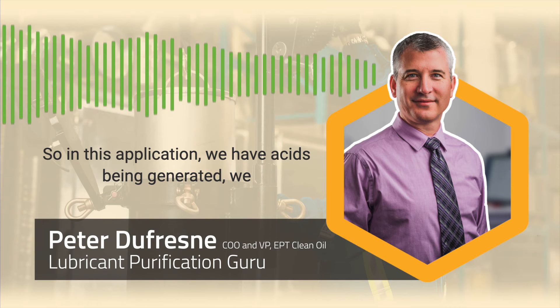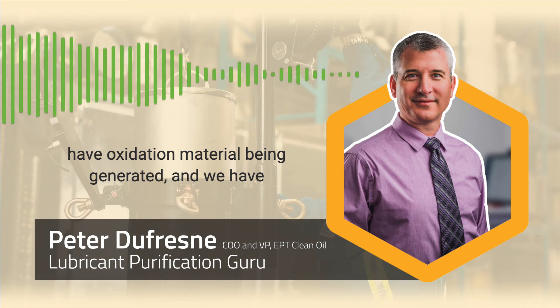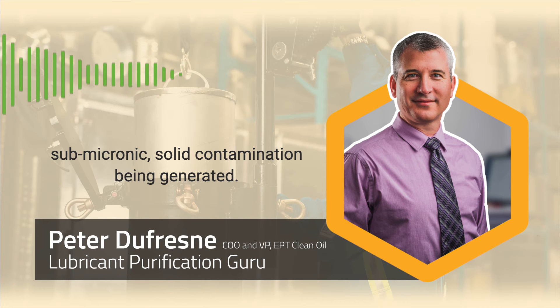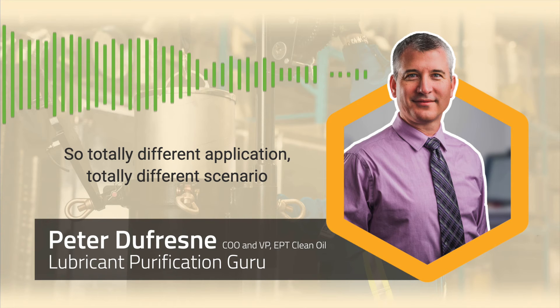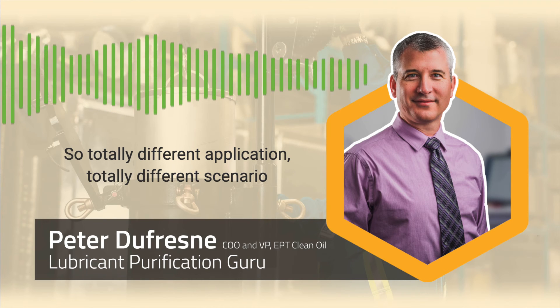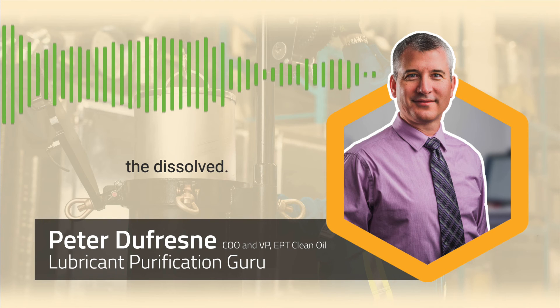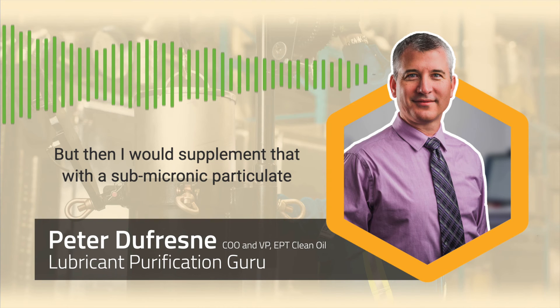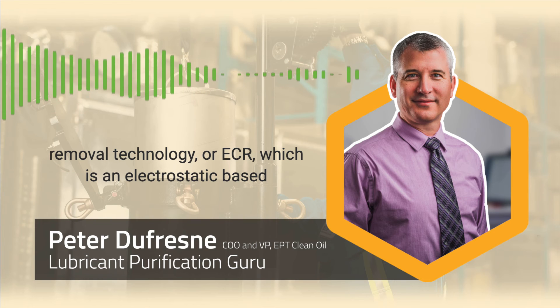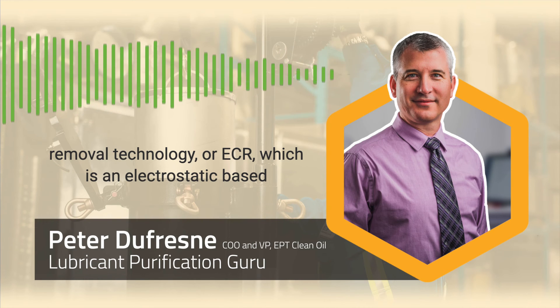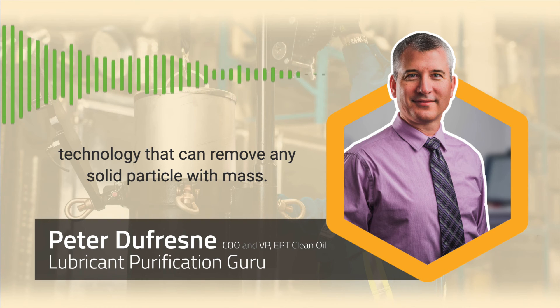In this application, we have acids being generated, oxidation material being generated, and submicronic solid contamination being generated. It's a totally different application and scenario, requiring a different lubricant conditioning system. So I would start with ICB ion exchange technology to remove the dissolved contamination, but then supplement that with a submicronic particulate removal technology, or ECR, which is an electrostatic-based technology that can remove any solid particle with mass.